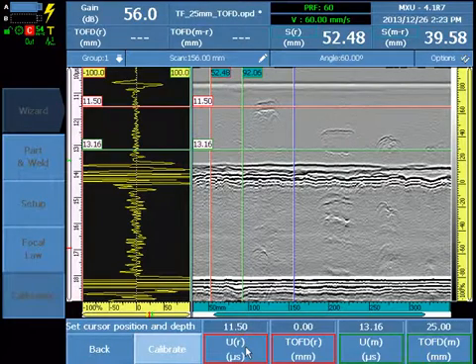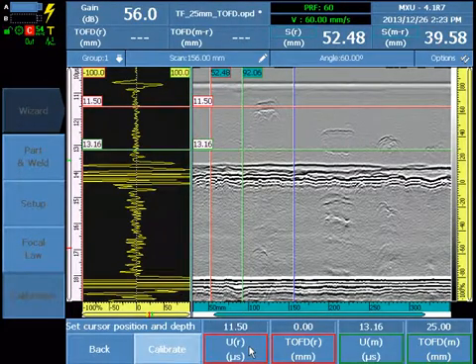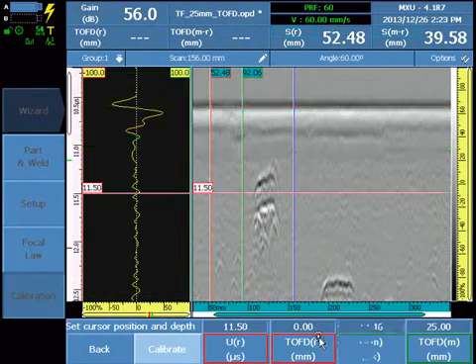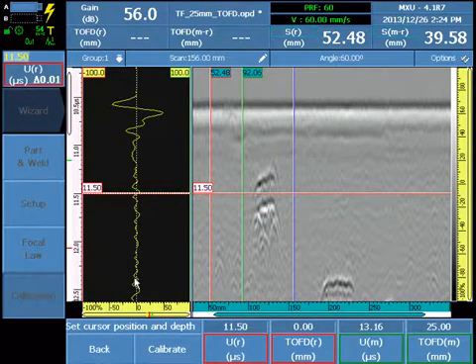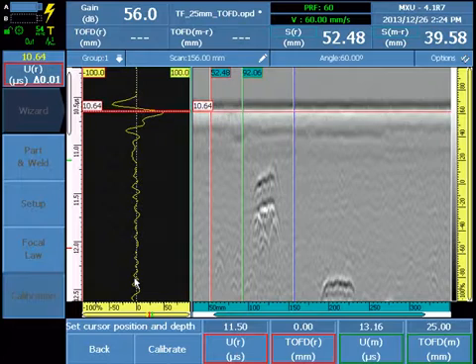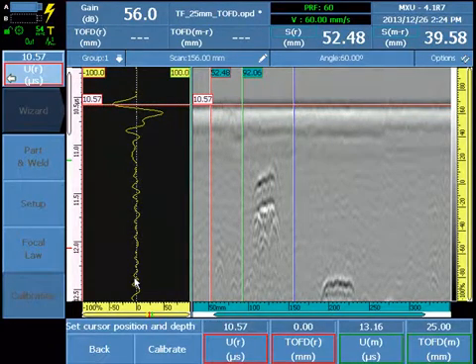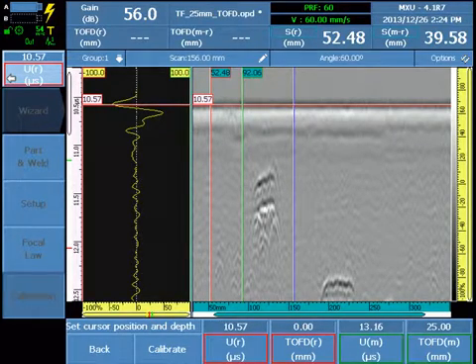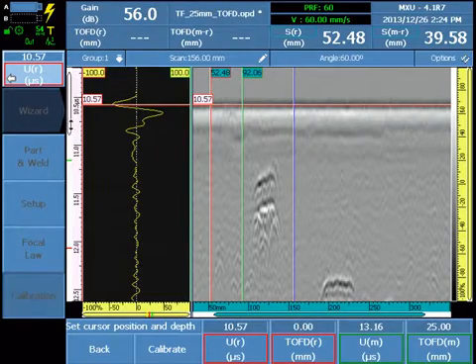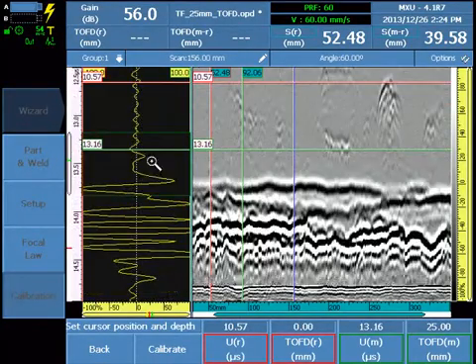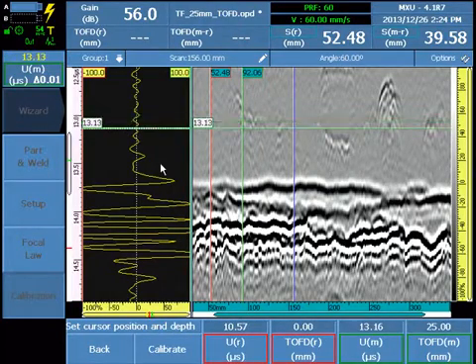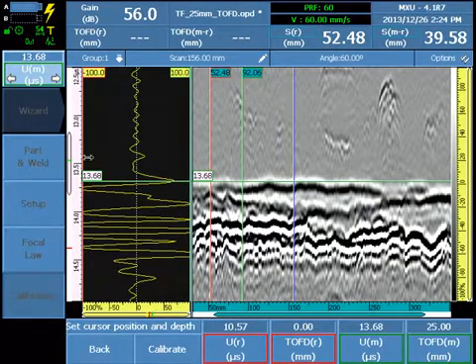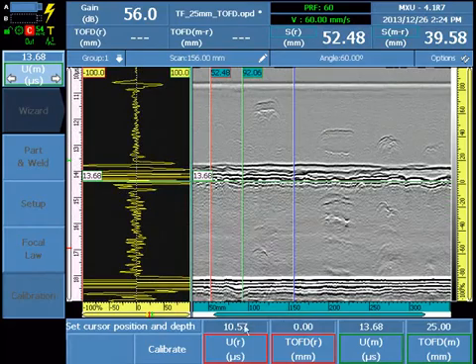The software is asking for two targets to be identified with the cursors. Target one is the lateral wave at zero millimeters, and we will use the cursor on the first negative peak of the lateral wave. For the back wall, we will place the measure cursor on the first positive peak of the back wall signal. Select calibrate.